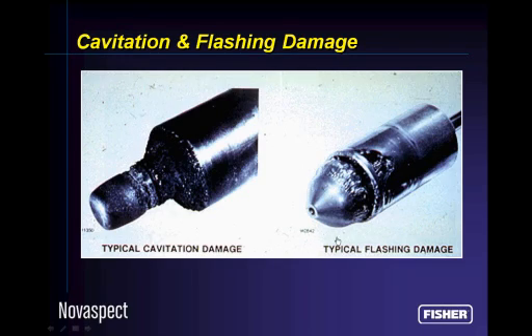The picture on the right is indicative of flashing damage. If that plug were made out of clay and you took a popsicle stick and started carving, gouging long pieces of that away, you would end up with a plug that probably would look like flashing damage. Usually it's a very shiny look and crevasse in nature. Cavitation damage, on the other hand, looks completely different. It's characterized by kind of a pitted lava rock, pumice stone look to it. It's quite obvious when you see it.